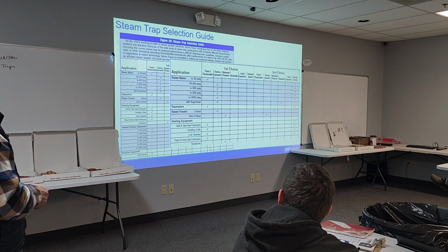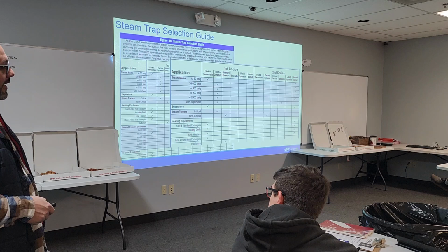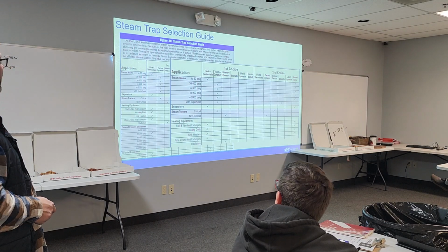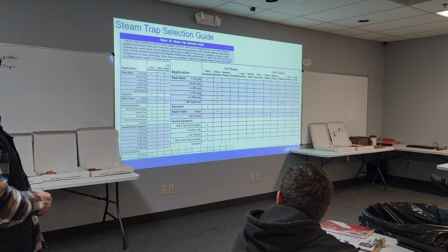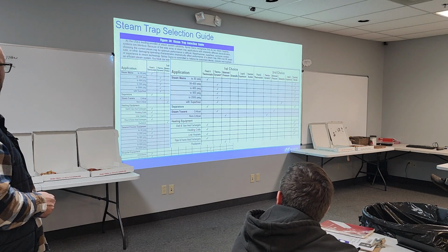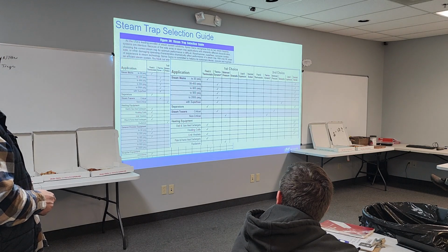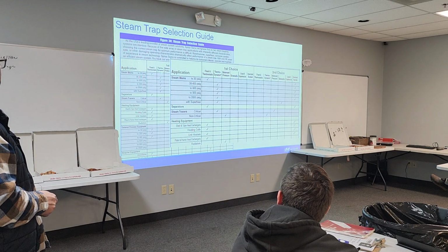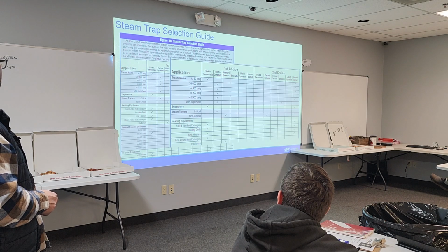That second choice, so that's though 230 psig. That's not my first choice. I don't like that trap in that application. They're saying the float and thermostatic 0 to 30, right? So that is in agreement 100% with what I believe. 30 to 400 psi, a TD trap, 0 to 600. They got the TD all the way down here until they get into a separator.